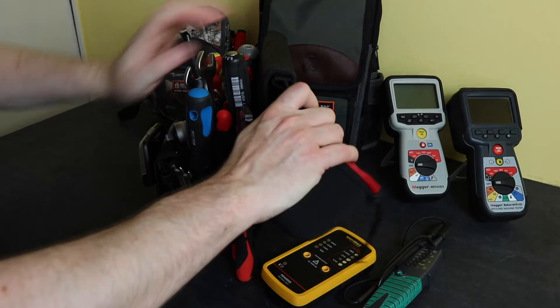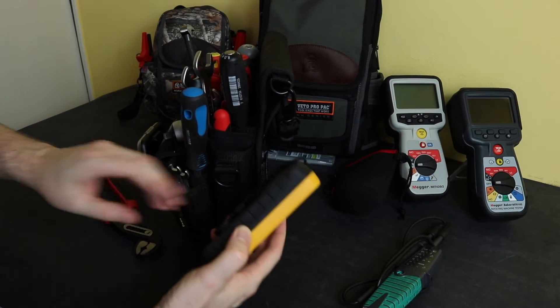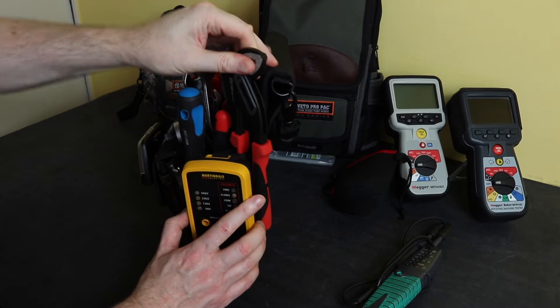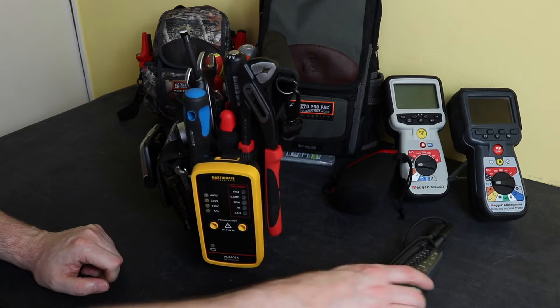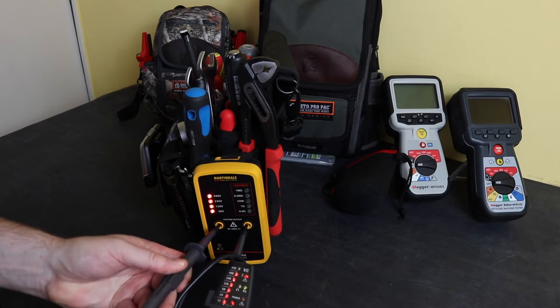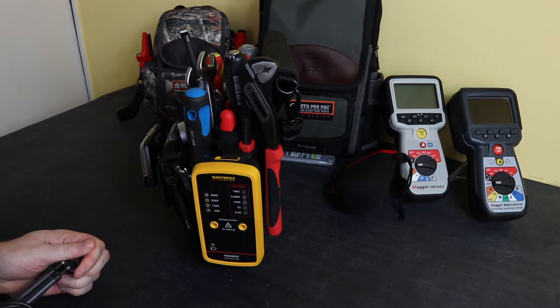At the moment I've got the proving unit stored in a little lens bag that clips to the D-ring — it seems the easiest way. The other way I had this set up was with the magnet that comes with the box anyway, so it's not an extra cost. You put it in there and hold it down with the grips, and carry it around that way. It's a little bit more exposed, but the advantage is as soon as you come to testing you can have it sat there ready — test your instrument, go test your motor terminals, then come back and test your instrument again. At the moment I'm sticking with the lens bag — it keeps it a little cleaner and out of the way.